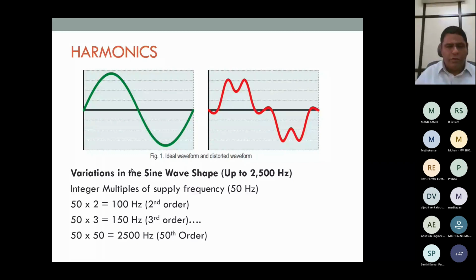So what is a harmonic? The left one, the green one, is a pure sinusoidal waveform. The right figure is the distorted waveform. What distortion happens here is called harmonic. So frequency from 50 hertz to 2500 hertz is termed as harmonics. It is an integer multiple, a whole number: 50 hertz, 100 hertz, 150 hertz, 200 hertz, like that till 2500 hertz. Every 50 hertz is given a whole number. The first 50 hertz is what we get as a supply, which is given number 1, the next 100 is given 2, the third 150 is given 3, and so on until the 50th harmonic, which is 2500 hertz, which is being tested and what we need to comply with.